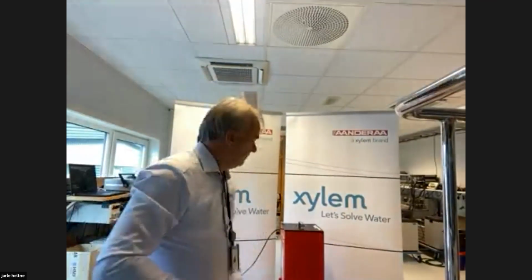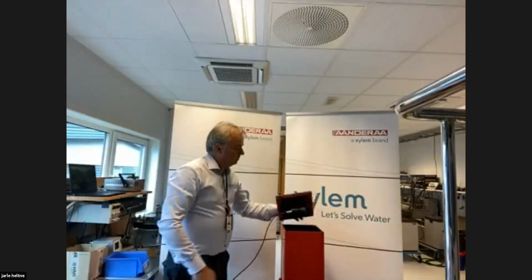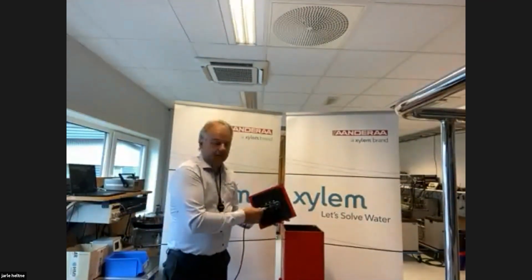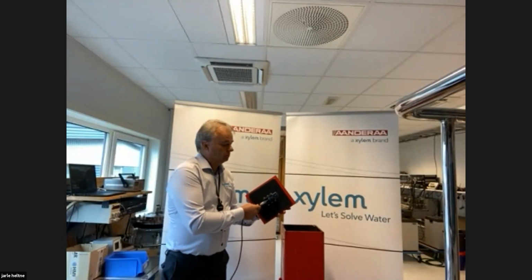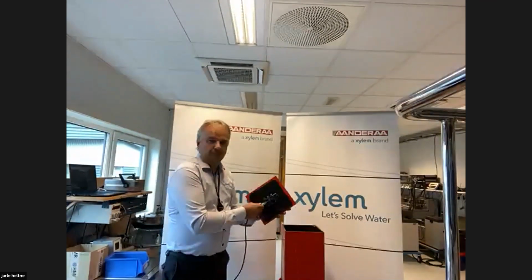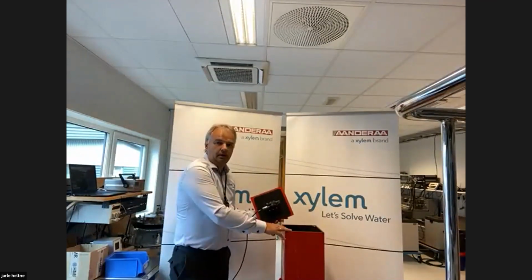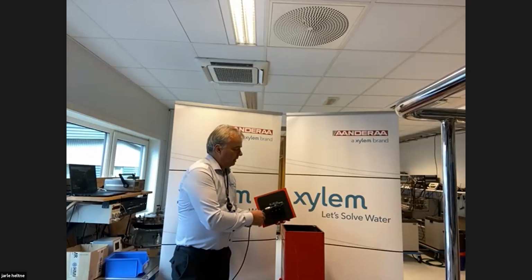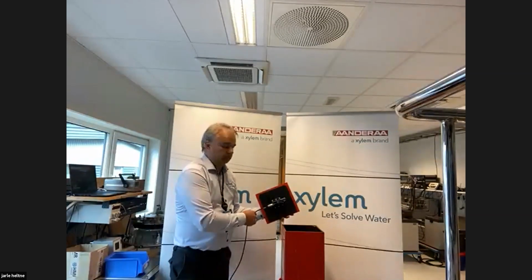So all our water quality sensors also have a temperature sensor inside. Since we are doing a multi-point calibration for the temperature, you will also get a high accuracy temperature measurement from the sensor. In this chamber and a similar chamber with different size, we calibrate the sensor in different concentrations of FNU.